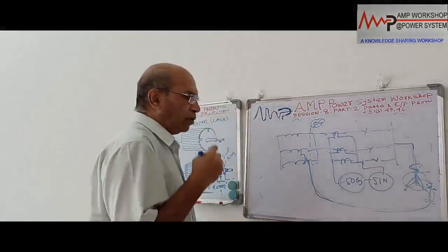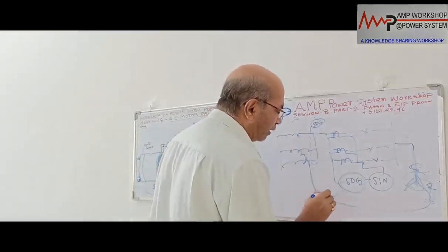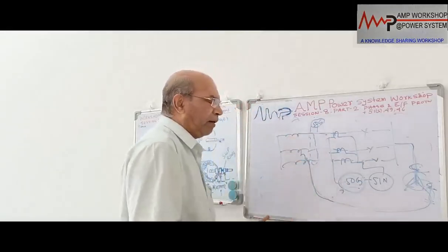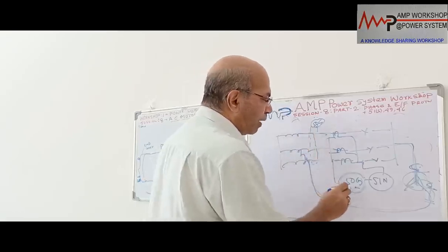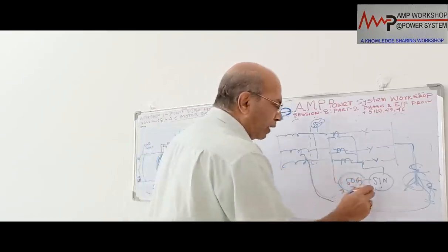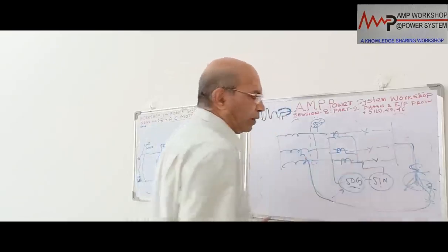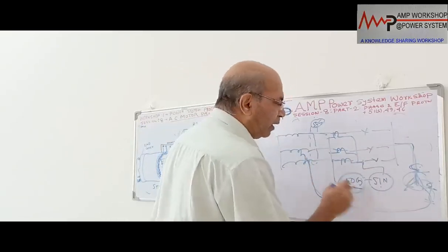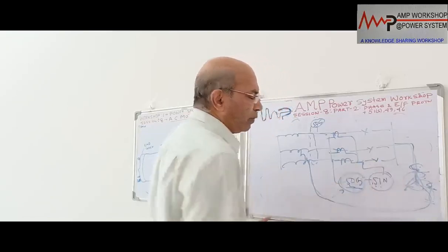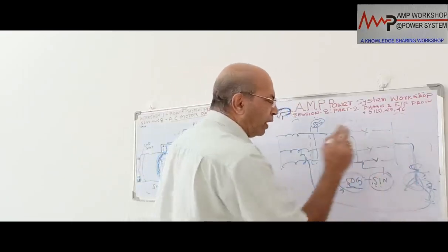Okay. So in case of earth fault current protection, we provide either this 50G or this 50G, any one of them. If the donut CT is there, then this 50G will not be there. But if we cannot put the donut CT, then we provide 50G along with 51N also. This 51N will protect the transformer with IDMT characteristics, so it can be easily coordinated with others. It will be a backup for the 50G, and it can be coordinated with this. If this 50 fails, then the 51N operates instead of the incomer side operating.